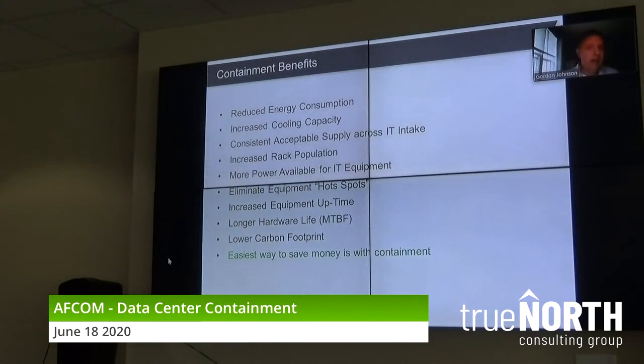Once I've achieved that, and only after I've achieved that, then I can go back and do what we mentioned at the beginning, and that's the cooling optimization in your data center. And again, what is cooling optimization? The first thing is raising the supply air temperatures of your cooling units. I want to get them as high as possible to still have your IT equipment running at a safe temperature. We'll talk about what that highest possible number is in just a moment.